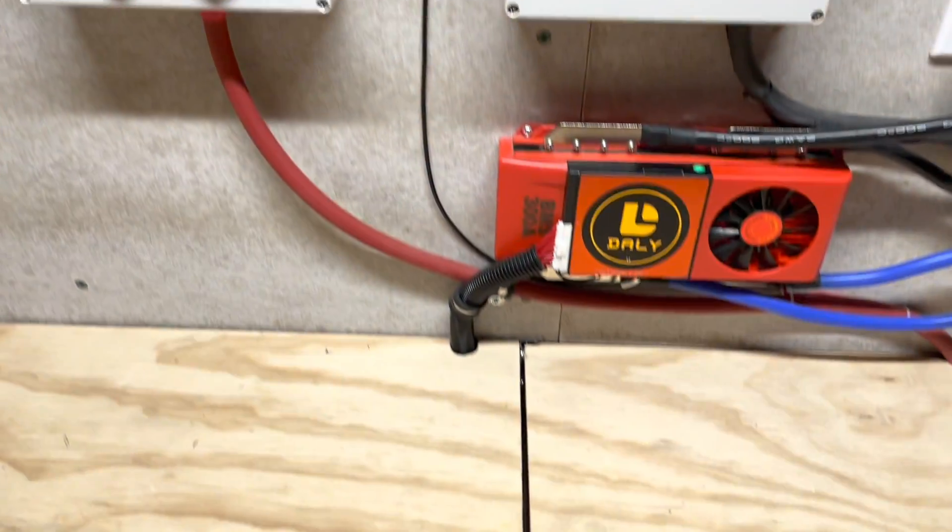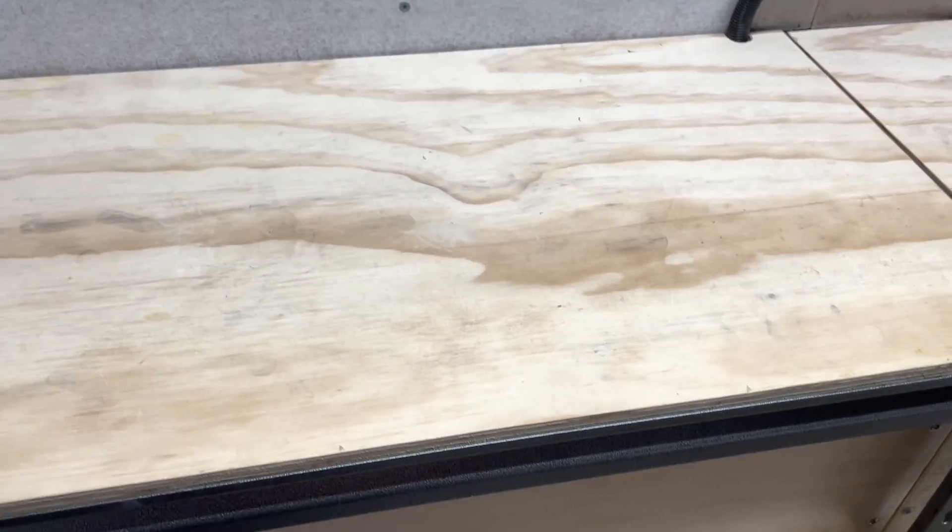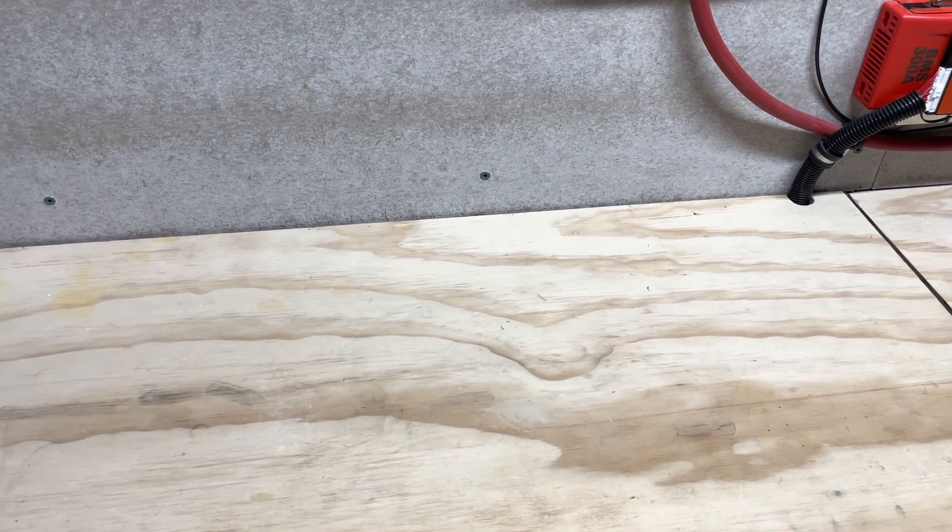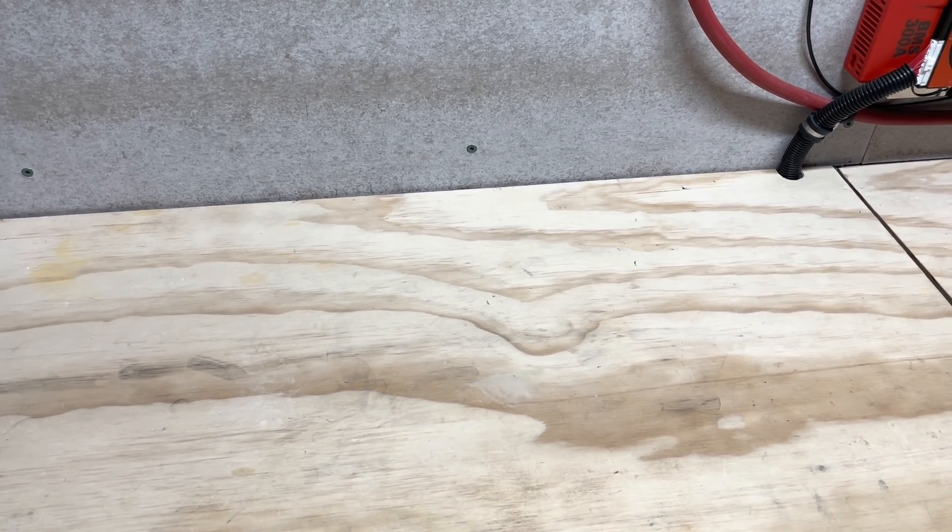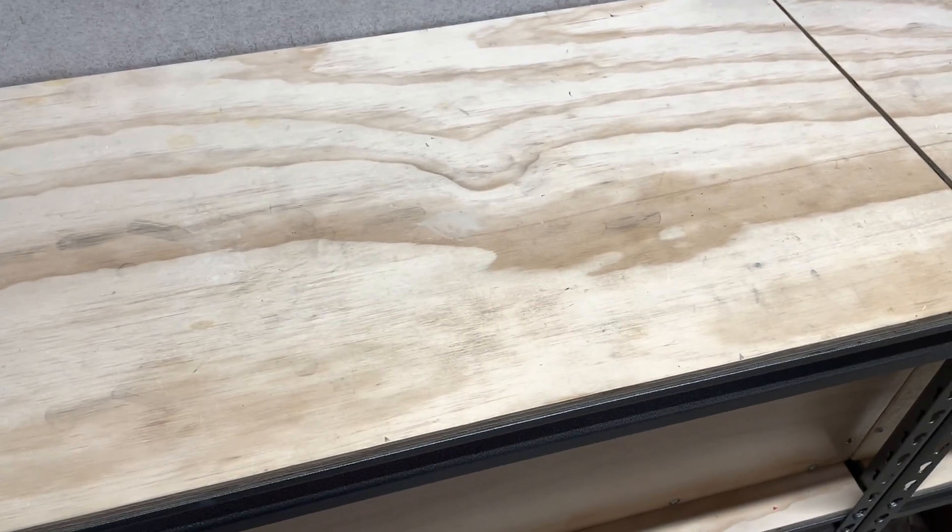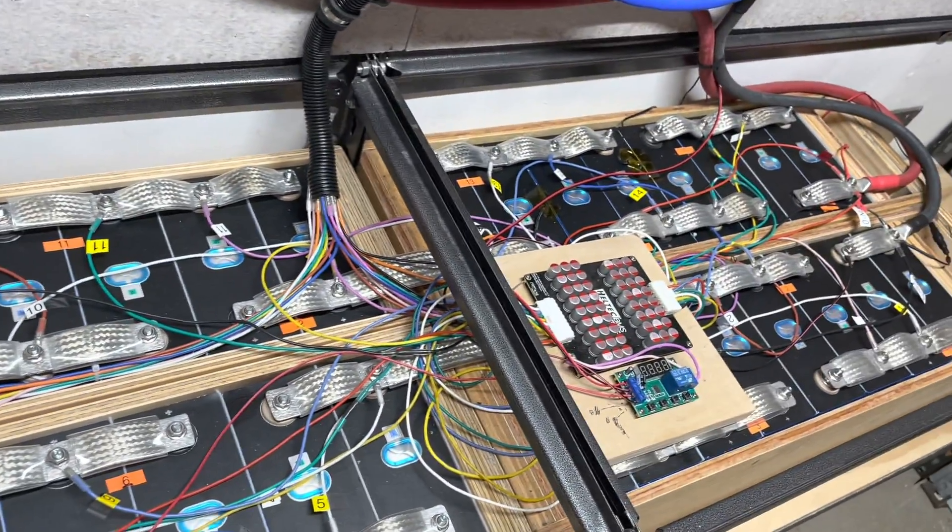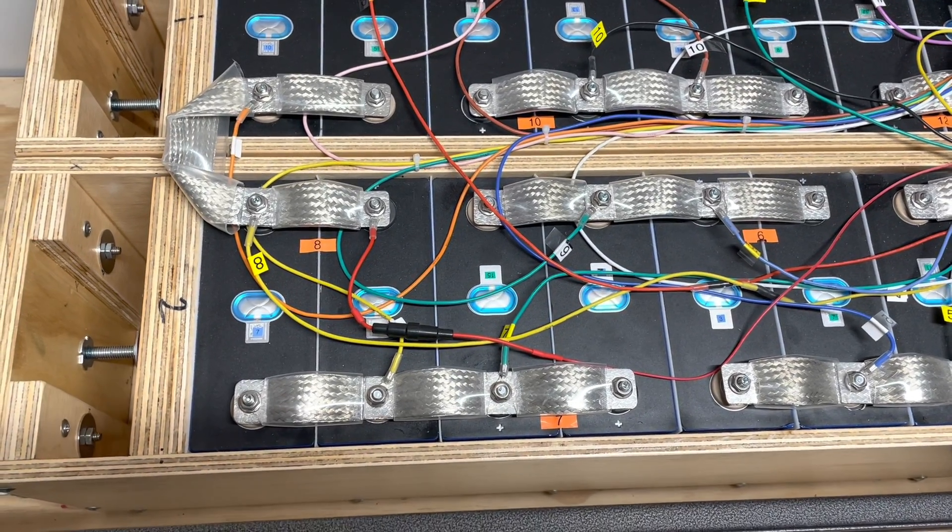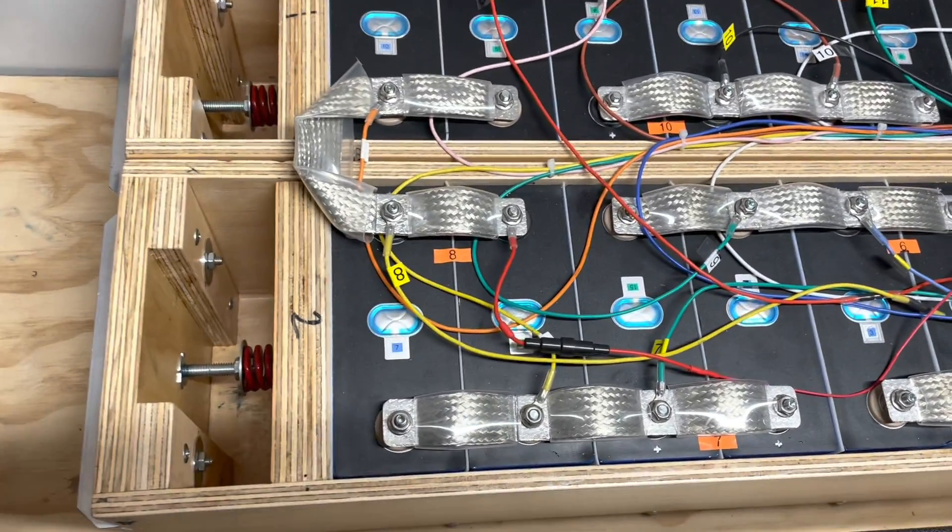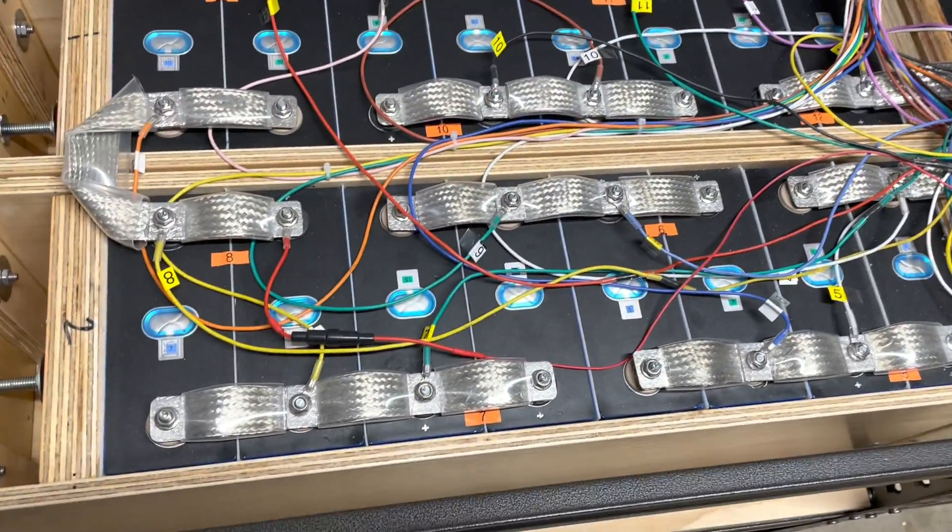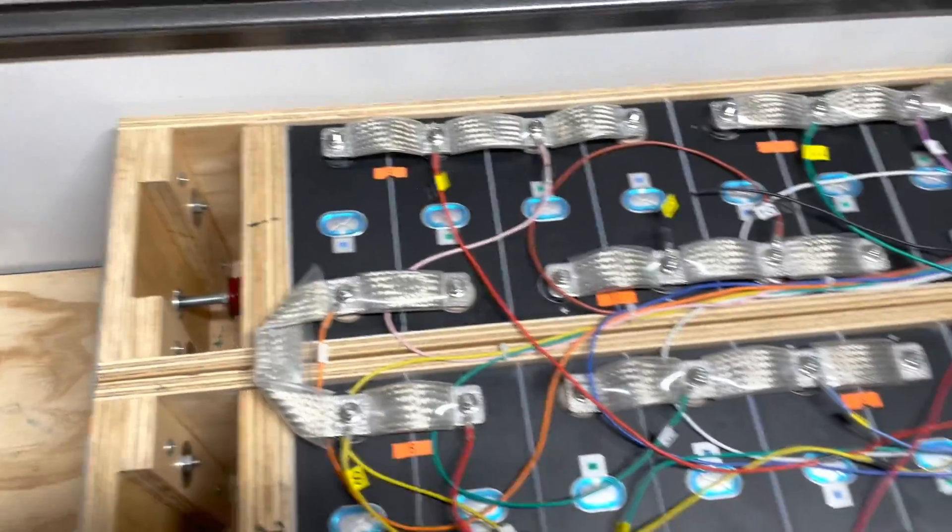I'll open the cover and we'll look at the batteries. Have enough capacity here to triple the capacity. The batteries are 32 kilowatt hour and they're CATL 310 amp hour cells, 32 of them. All right, I got the bench cover removed. Now you can see the batteries. They're 2P 16 series configuration and they're compressed. There's four modules here with eight cells per module. Each module weighs a hundred pounds, so it's pretty easy to move them around.